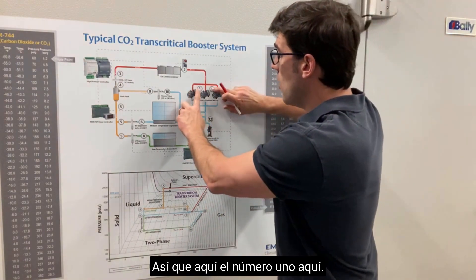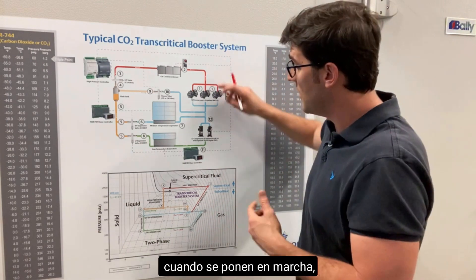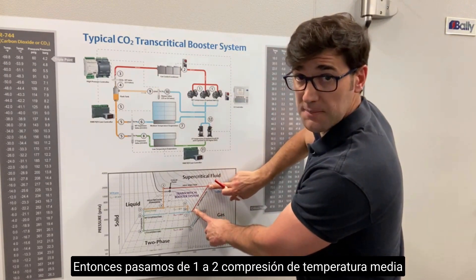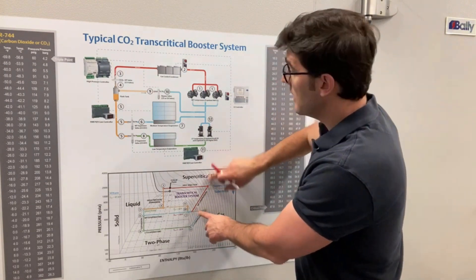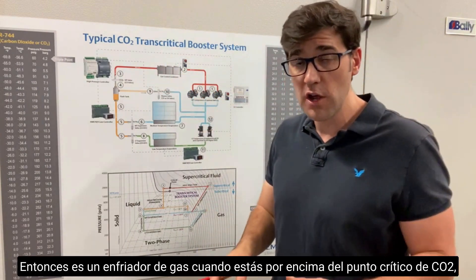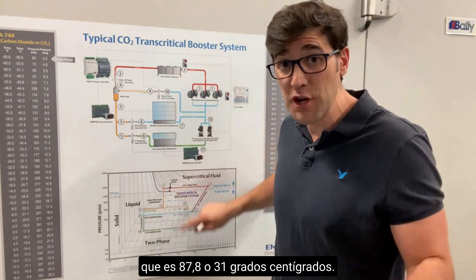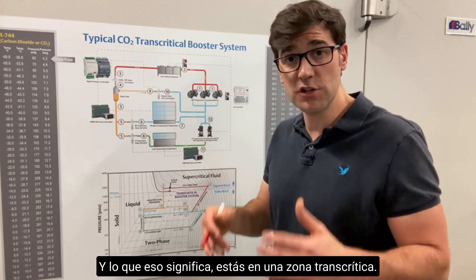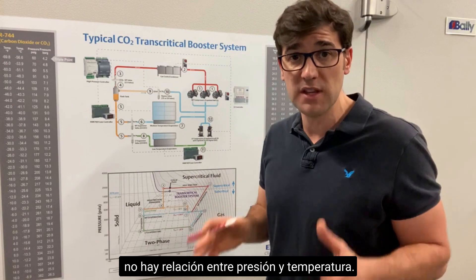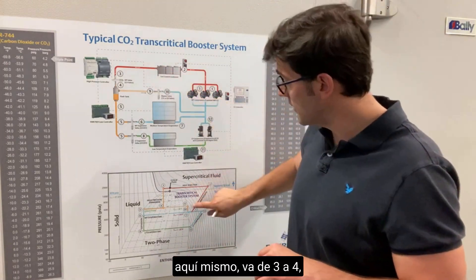Number one here represents the medium temp compressors — Copeland's 4MTLS compressors. From one to two is the discharge, so we go from one to two through medium temp compression into what we call a gas cooler or condenser. It's a gas cooler when you're above CO2's critical point, which is 87.8°F or 31°C, meaning you're in the transcritical zone where CO2 is a supercritical fluid with no pressure-temperature relationship.